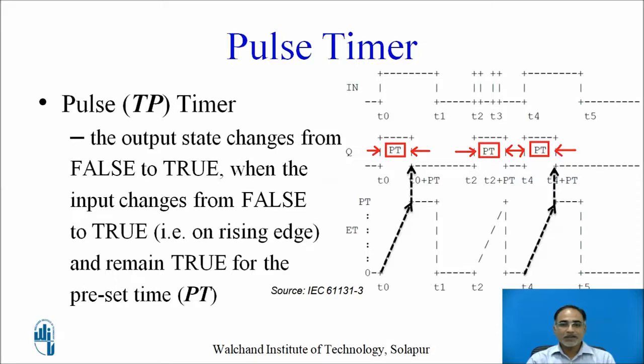The output state of a pulse timer changes from false to true when the input changes from false to true — that is, on the rising edge of the input. At instant T0, the input changes from 0 to 1, and at the same time the timer output Q also changes from 0 to 1. The output remains true for the preset time PT, so the output remains true up to T0 plus PT, giving a pulse width of PT duration.